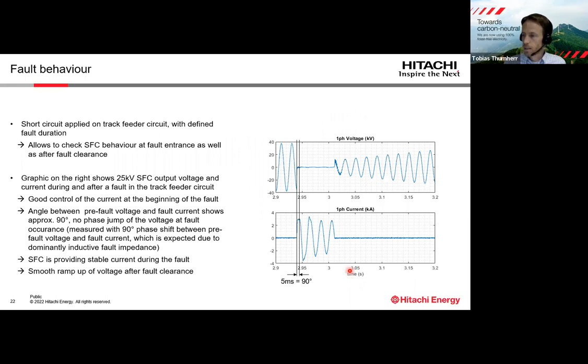And you can see here an example of the measurements that were taken. A fault with a very low impedance was applied for a certain time, and this allowed us to observe the behavior at the fault entrance, during the fault, and also at fault clearance afterwards. We can see the single phase voltage here and the single phase current of the static frequency converter. And I think what we can observe here is that there is good control of the current during the fault. It's a stable current that the SFC provides.